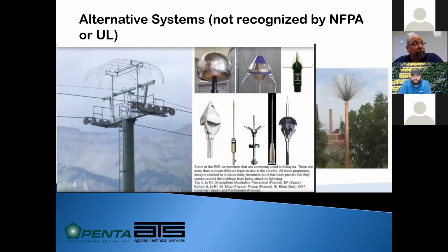So instead of having an air terminal every 20 feet around the perimeter of the building, their claim is we can put one air terminal on top of your building and it's going to protect your entire building. This is a dissipator array air terminal. By making all these small points, their claim is that lightning will be attracted here versus other larger points. What we've seen happen with this type of air terminal, the one on the far right, is if that gets struck, all of these little small points turn into molten metal that then rains down on your roof.